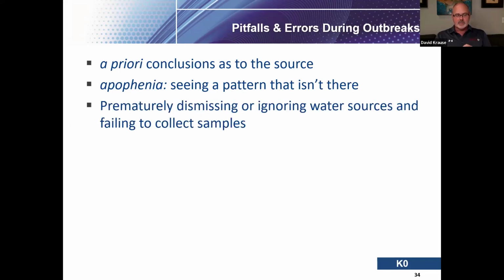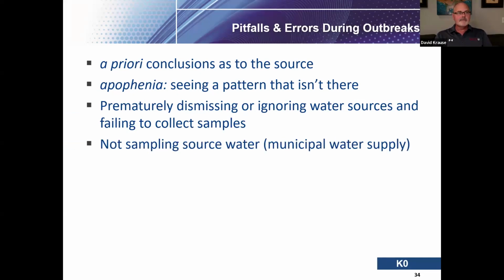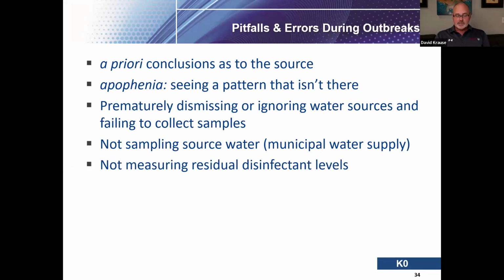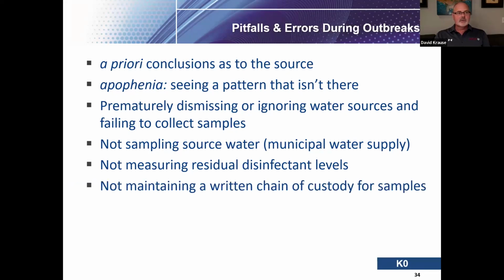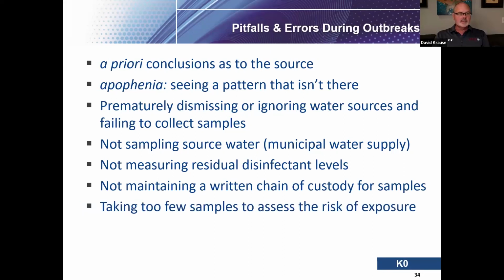Ruling out other sources is another initial pitfall — prematurely dismissing or ignoring water sources, and failing to collect any samples during the relevant time. Not sampling the municipal water supply. Not understanding the water quality, the conditions, and the organisms that may be coming in with that. Not measuring residual disinfectant levels, not maintaining a written chain of custody for samples — they do get mixed up. Taking too few samples to assess the risk of exposure: in a 54-story building, taking 12 samples is not enough.